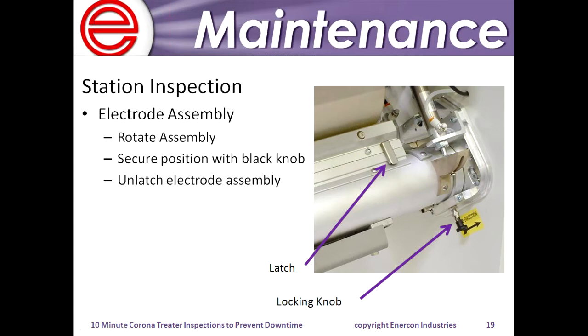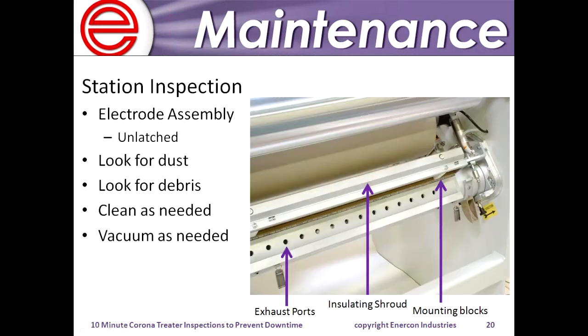So then you can work on and perform the cleaning and everything with the electrode assembly out of the treat position, and to hold it in place while you're carrying out the maintenance. We also have these latches that go down the length of the electrode assembly. Loosen those, and that's going to allow the electrode assembly to pop open. As shown here, it exposes the underside of the electrode assembly, and we're enabled to clean the exhaust cooling ports and everything.